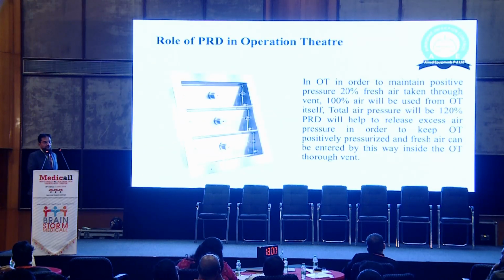Then this is the PRD. You know the importance of the PRD. If you don't put this PRD in your OT, you will not get the positive pressure. Why? If the fresh air is coming in and there is no pressure release damper, fresh air will not come inside. So this is also one of the important parts.